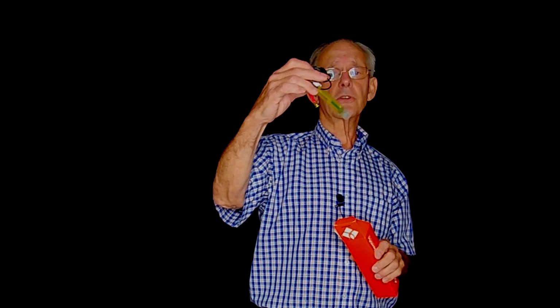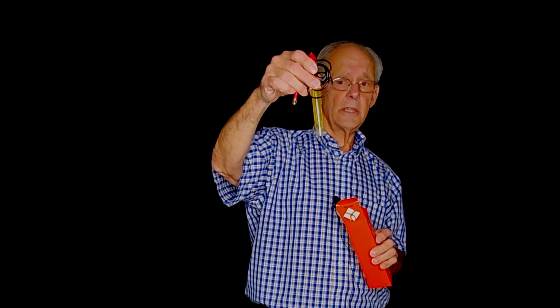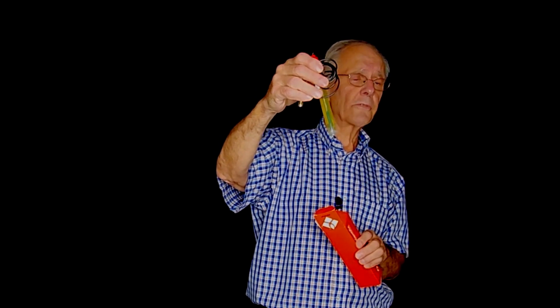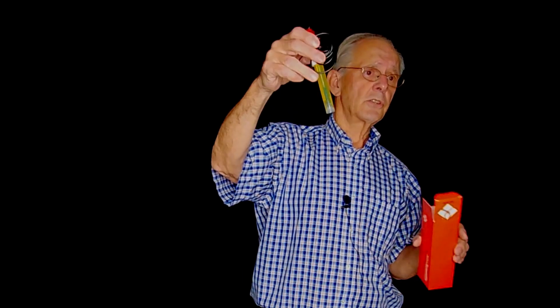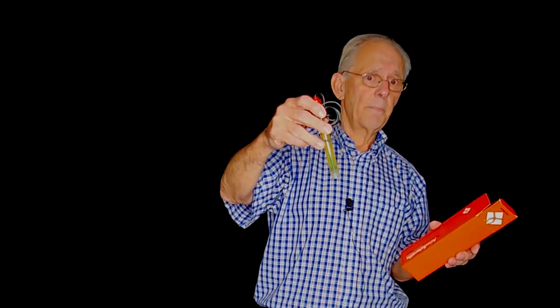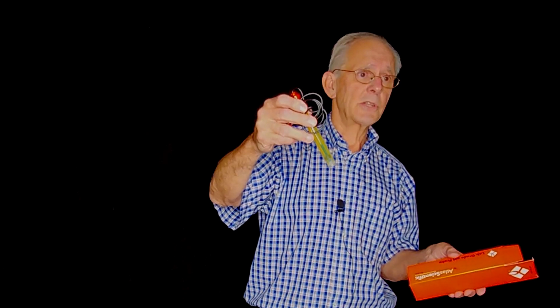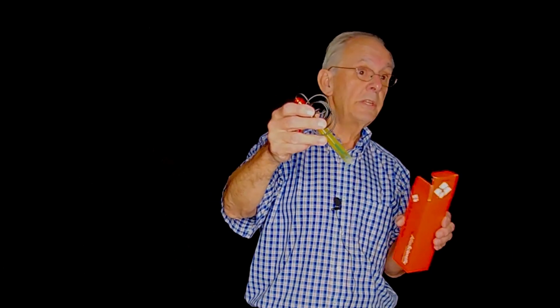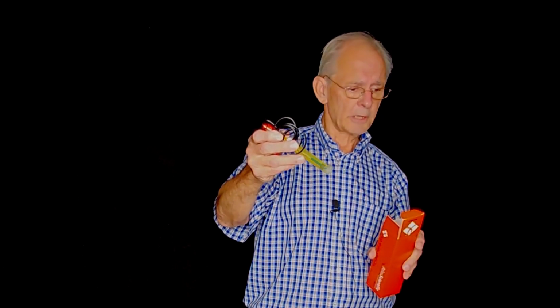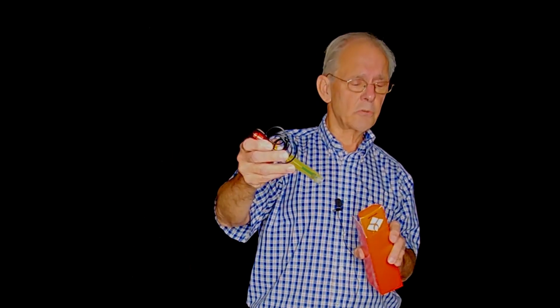This is a sensor that detects pH, which tells the difference between acids and bases. A pH of 7 is neutral, higher pH is a base, and lower pH is an acid. This is used in water applications to judge whether you need to add acids or caustics to get a neutral pH. It's used in both wastewater and clean water processes, and heavily used in industry wherever liquids are involved, since pH is a very important value to measure.